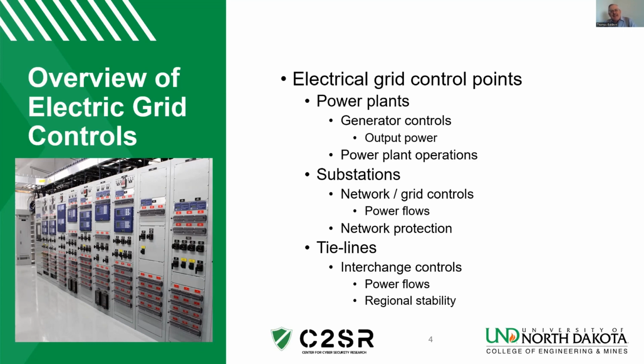One is the plant control for providing the prime mover, the rotating shaft to go to the generator. And then there's the power controls from the generator connected to the grid. So our voltage, excitation, and our governor are all there on the second level of control. In substations, we have our grid controls so that we can effectively make sure that power is flowing in the right direction with the correct reactive power compensation for us to run efficiently, and network protection in the background, constantly monitoring, hopefully used rarely, to take care of abnormal events and making decisions on how we are going to correct those events. This includes non-fault events, and so this would be things like watching for swings in the power system.